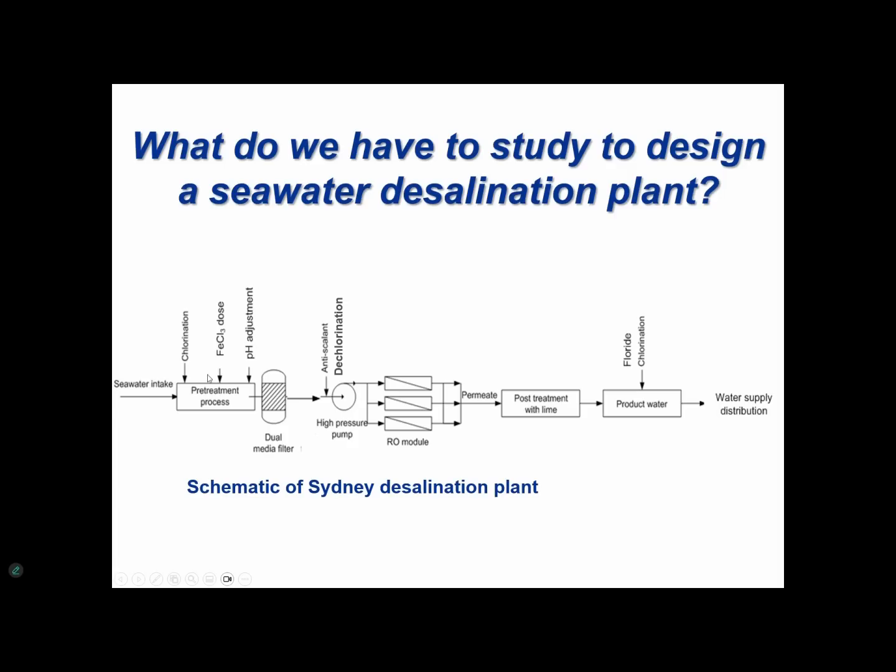And pH adjustment. Initially seawater is pH 8, and pH 8 has a high concentration of hydroxide, which can easily combine with calcium, magnesium, or multivalent iron. Ultimately, when you have 50% recovery, you have a lot of inorganic fouling occurring in this reverse osmosis membrane. So pH adjustment is necessary to avoid the inorganic fouling to achieve the overall 50% water recovery.